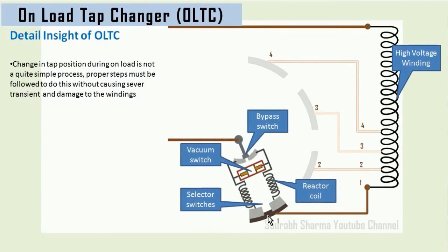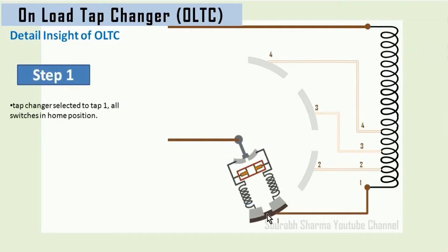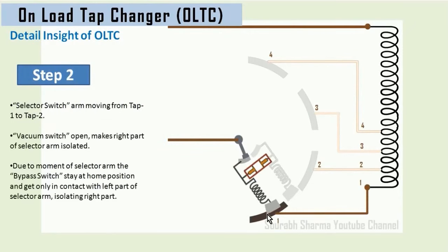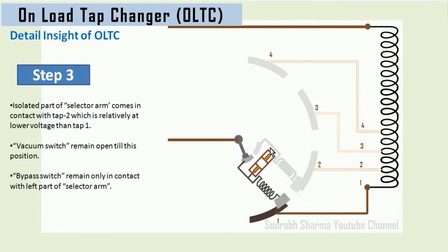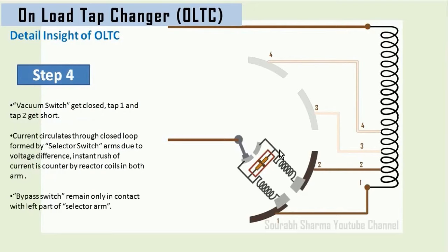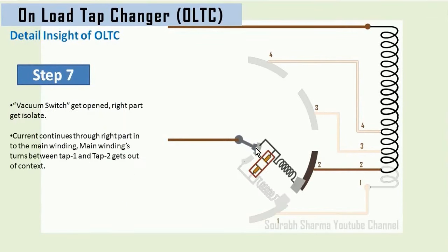The arm is connected on tap 1. When the output voltage of the secondary winding gets reduced due to heavy load, the arm must shift from tap 1 to tap 2, because the active number of turns at HV must be reduced to increase the secondary voltage. The sequence followed is: first, the front part — the selector arm — moves a bit so that the right part gets freed from tap 1, as the vacuum switch is already open, and now there is no voltage on the right part. Due to further movement, the right part gets in contact with tap 2, which is at slightly less voltage than tap 1. Now the vacuum switch operates so that tap 1 and tap 2 get in contact and the voltage of both taps becomes equal. Due to this sudden closed circuit, a current circulates in the loop, which is limited by the reactor coils. Now the bypass switch can completely move to the right part and the vacuum switch becomes open, isolating the left part and therefore tap 1.